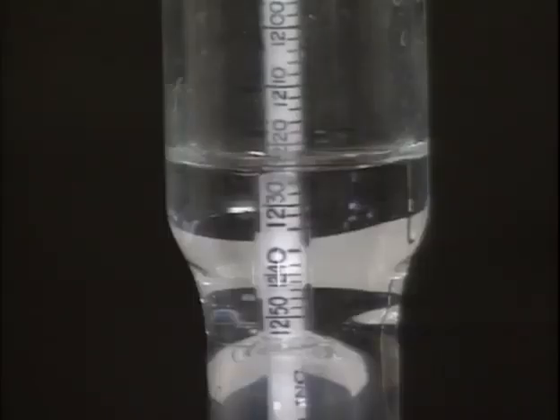Once the float steadies, the specific gravity is read off the scale at the surface of the electrolyte. The specific gravity reading here is 1.222. This is not necessarily the value that's recorded.